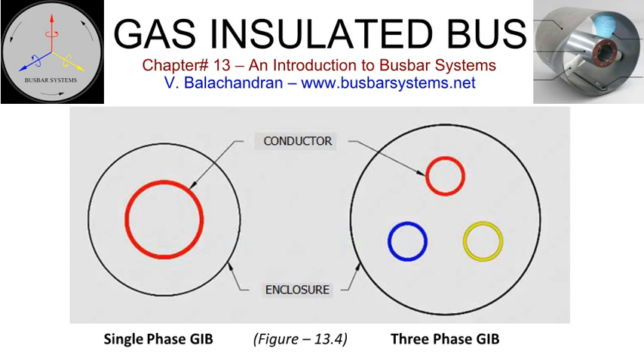3-phase gas-insulated buses have been installed for short lengths, at lower system voltages, when they are coupled to a 3-phase GIS unit. Since the phase spacing is minimal and the conductors do not have a shield, the short circuit forces will be far more severe in a 3-phase configuration than in a single-phase configuration. The enclosure losses will be far less in a 3-phase configuration than in a single-phase configuration for the same rating.